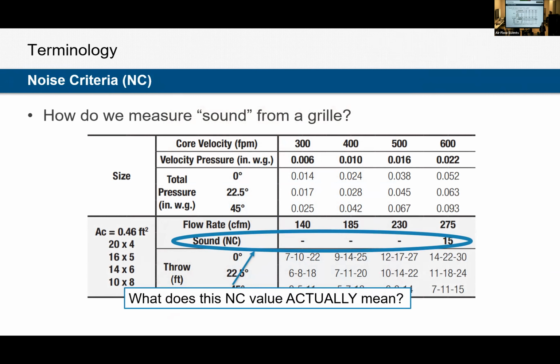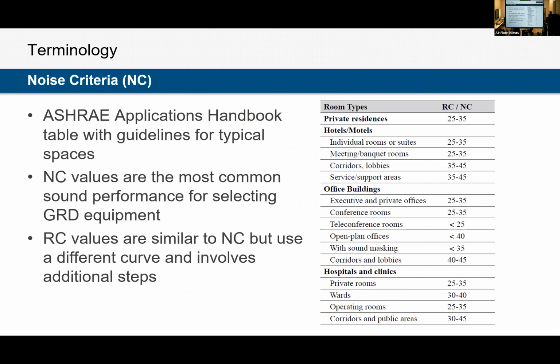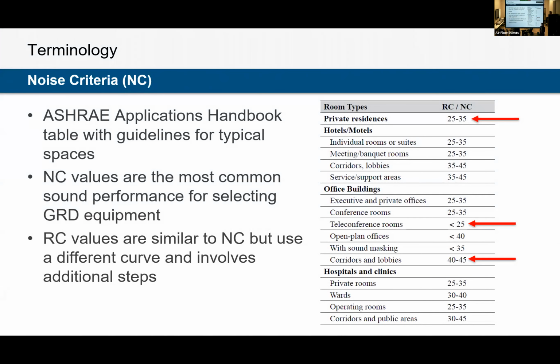Sound and NC is another very common catalog or scheduled piece of information. We obviously just talked about sound with Mauricio, but NC as far as diffusers, this is your sound level right at that one air outlet, but it is assuming a ton of things. ASHRAE gives this really nice chart with recommended NC levels for each different type of space, but what NC doesn't account for is different types of spaces. The NC number that you'll see in a catalog is assuming that there's carpet in the space, that there's lined duct upstream of the diffuser, assuming there's a certain amount of absorption in the space. It's assuming a lot of things that might not be true of all spaces.